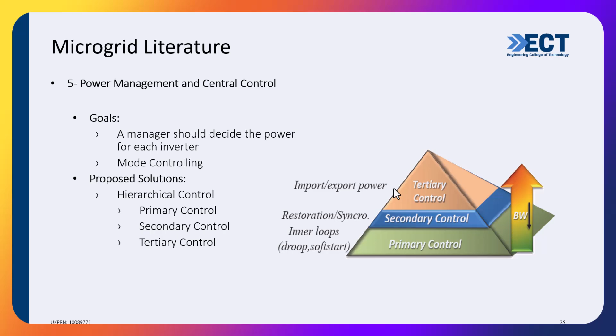One of the points I personally worked on is called paralleling inverters operating in island mode. I want to reduce the circulating current between inverters. We don't want, for example, my generated power to go to my neighbor by error or mismanagement. We call it circulating. That might happen if we have a very tiny deviation, and you end up losing that power without being paid for it, or you destabilize the system. So we want to reduce the circulating power.